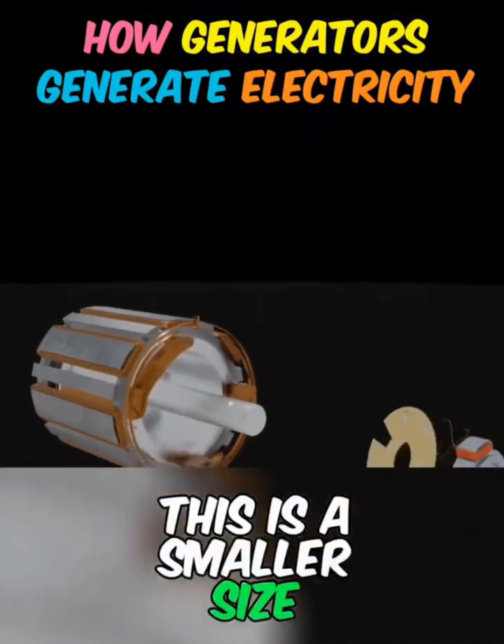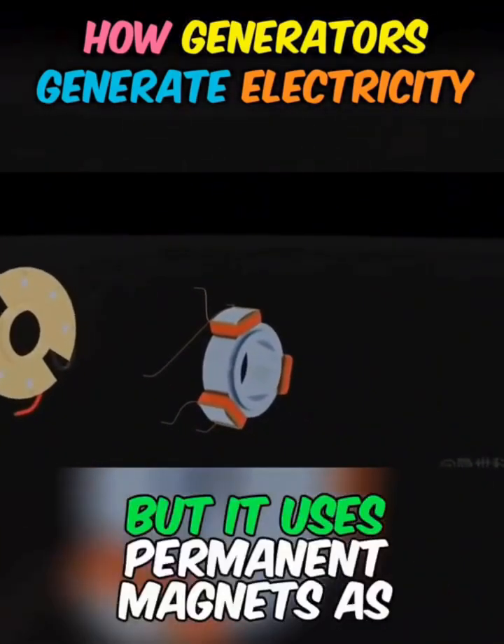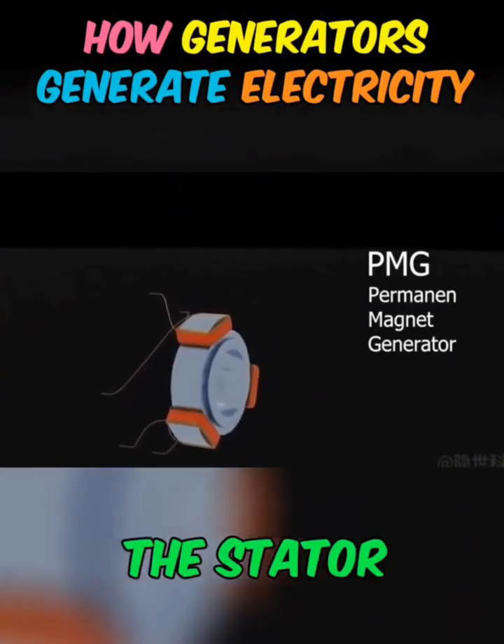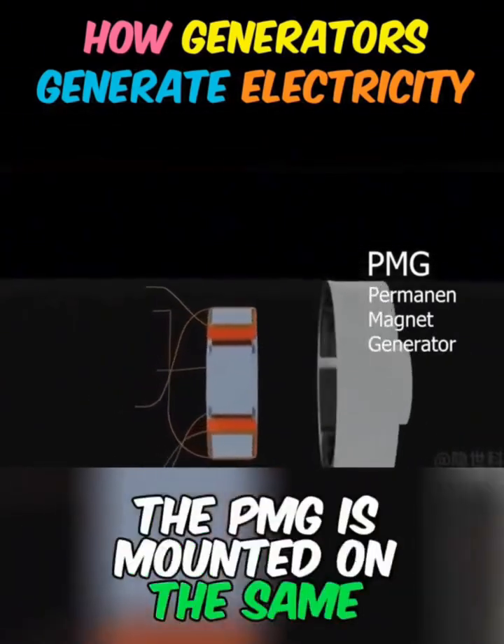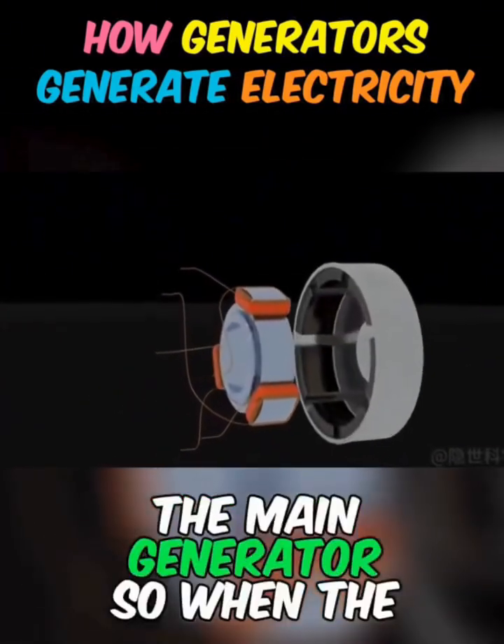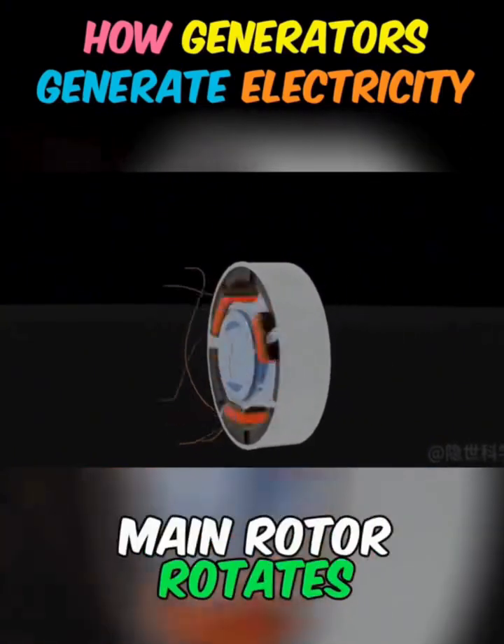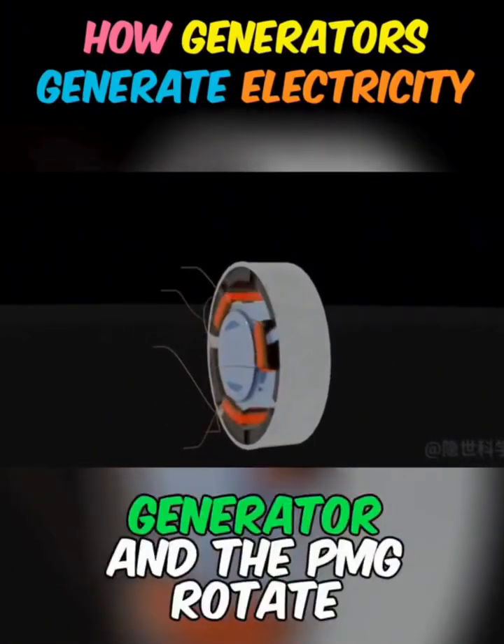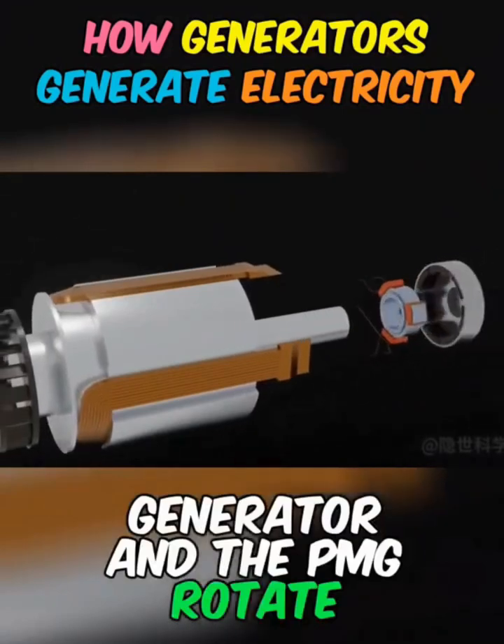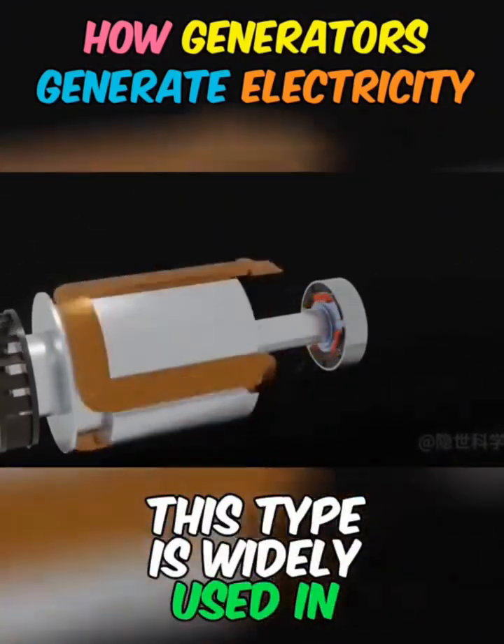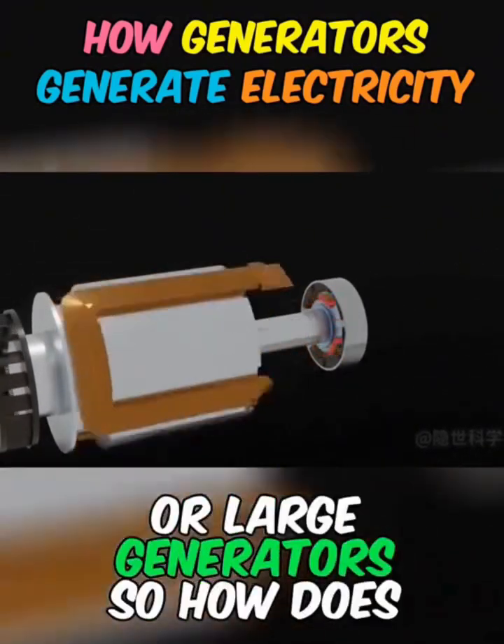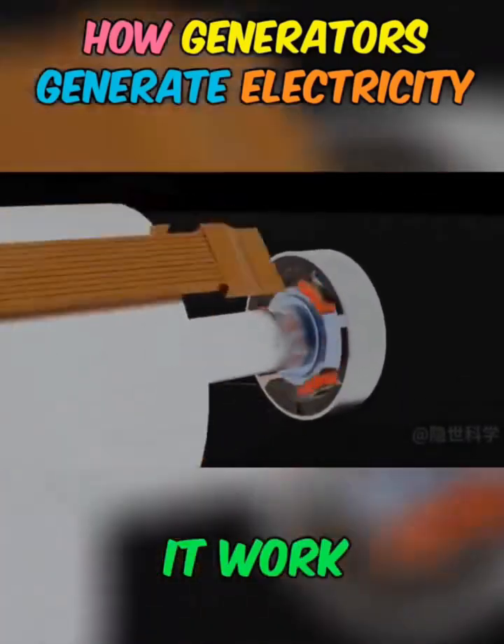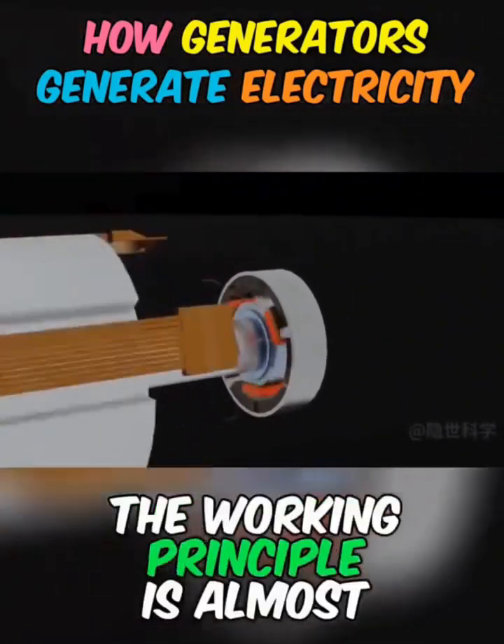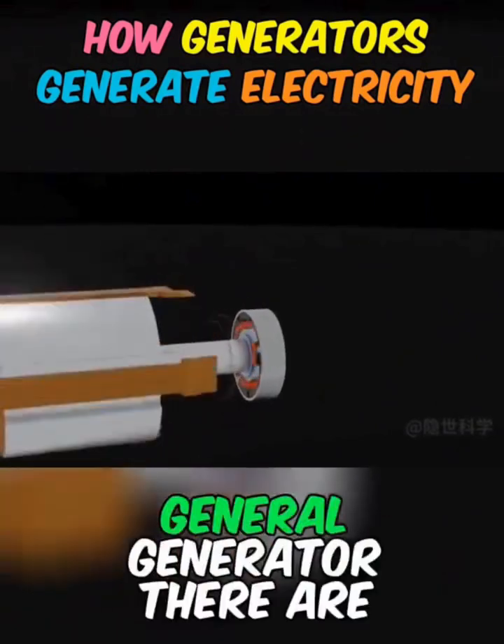This is a smaller size generator, but it uses permanent magnets as the stator. The PMG is mounted on the same shaft as the main generator, so when the main rotor rotates, both the rotors of the generator and the PMG rotate. This type is widely used in generator sets or large generators. So, how does it work? The working principle is almost the same as a general generator.